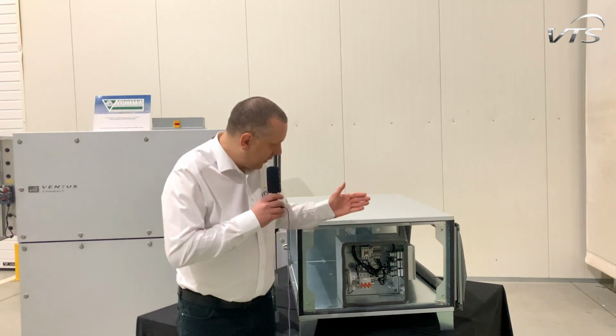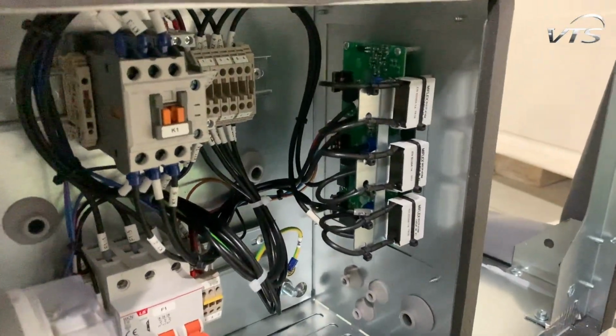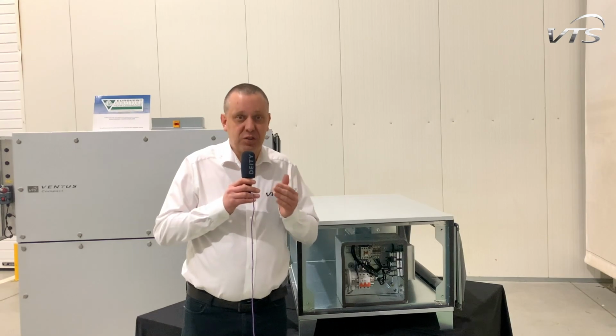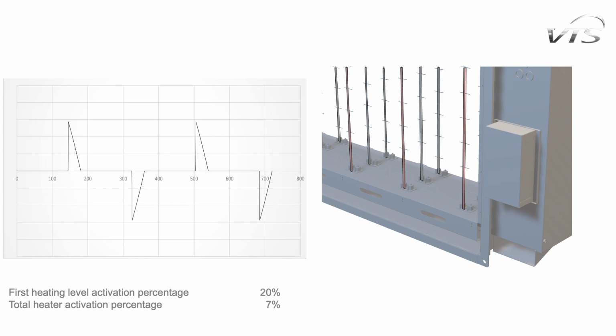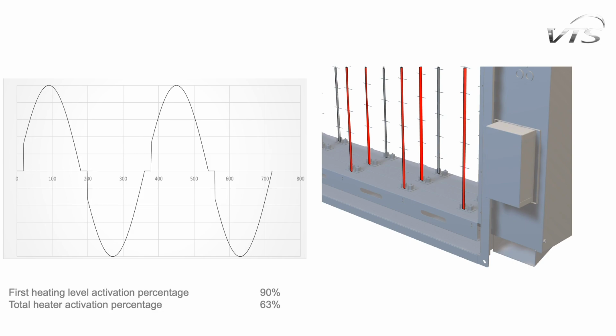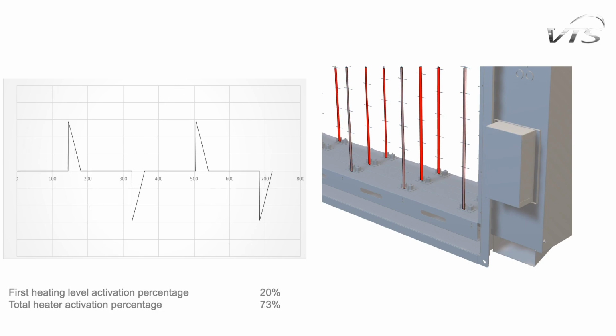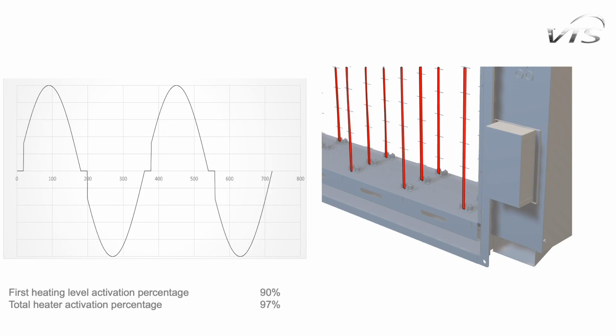Specially for this, we applied an advanced solution to the heater's junction box, which is capable of adjusting the current heating capacity smoothly and precisely. Solid-state relay. The solid-state relay can adjust the heating capacity by means of supplying current phase modulation. This method makes the output power of the electric heater always precisely set. When more and more heating is required, the heating elements light more intensively and keep your air at the required temperature.